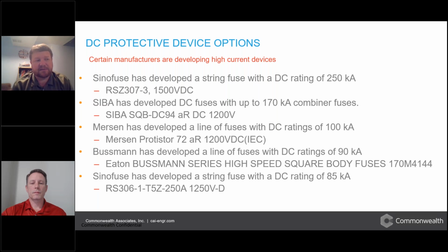But just like Chris was saying moments ago, the DC fuses can operate very, very quickly, and it's hard to put that into scale. For most of us that work in the AC world, we're used to fuses that trip in the order of cycles. A fast fuse may trip for a very high fault current in a cycle, maybe a couple of cycles. In the DC world, we're talking about fuse times that can be a 32nd or a 64th of a cycle, if we're thinking in that cycle terminology from the AC world. So that's where Chris was going with the 500 microsecond constants. Chris, can you back up a slide real quick?